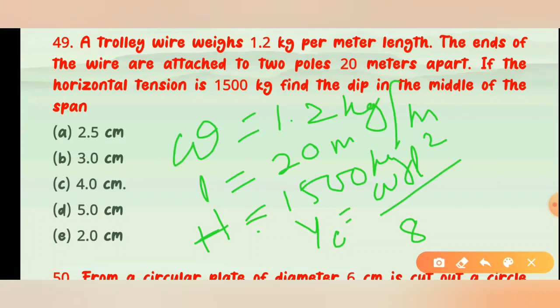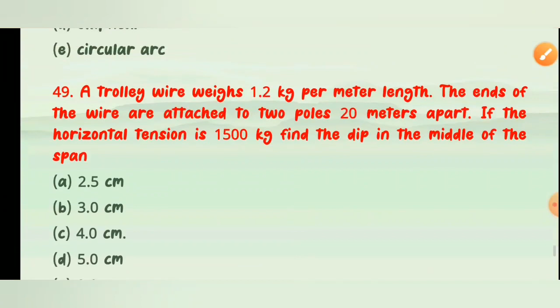Therefore the dip Yc equals omega L square by 8H. Yc equals omega L square by 8H, equals 1.2 into 20 square, 400, by 8 into 1500 meter, because this was kg per meter into meter square, kg meter by kg meter. 20 cancels, giving 1.2 by 30, that is 0.4 by 10, equal to 0.04 meter, equal to 4 cm. The formula is the central dip Yc equals omega L square by 8H.